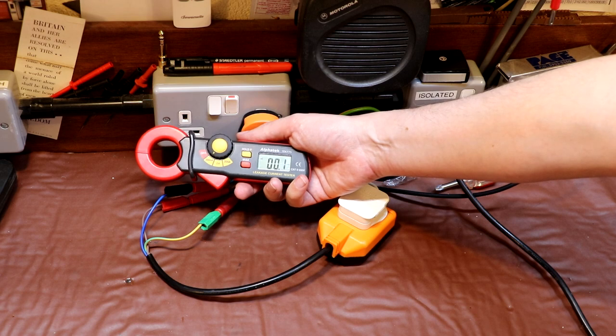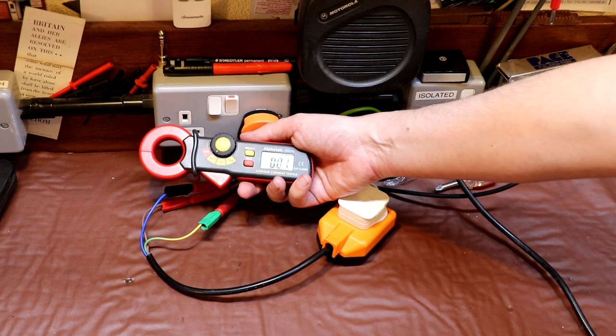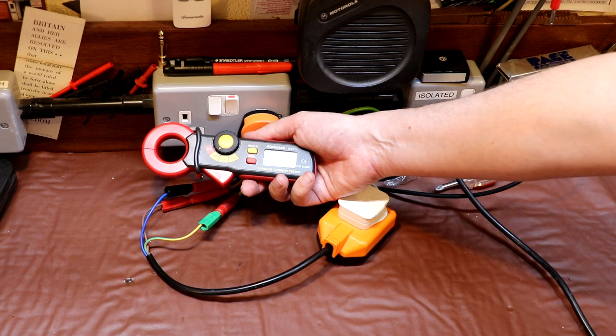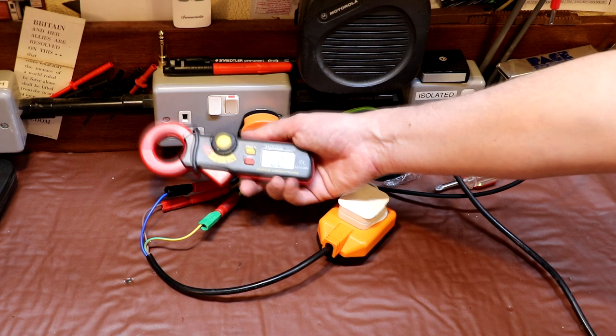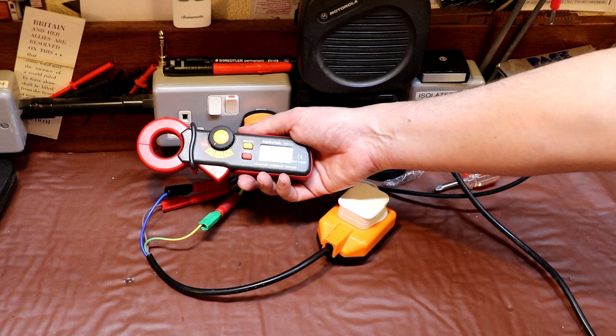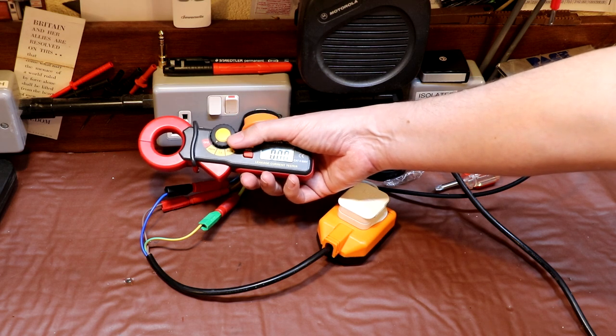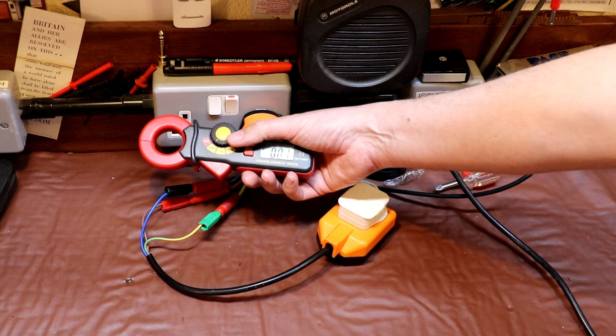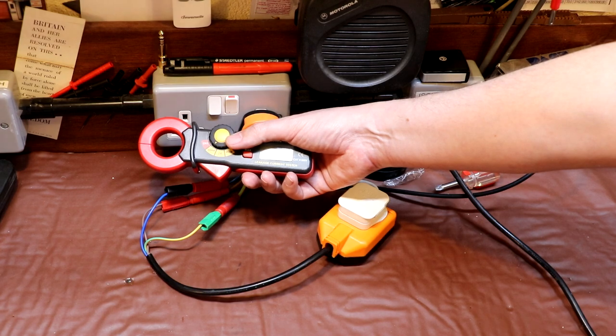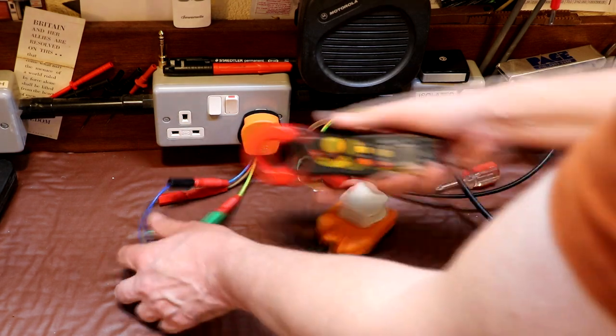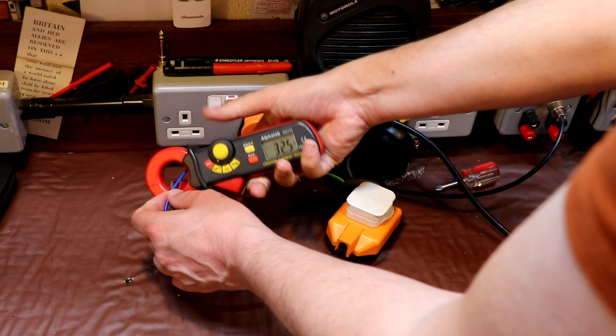So this clamp meter is made by Alphatec, and for those playing along at home, it's the Alphatec Tech 775. It is a little bit unfair to compare the Alphatec meter here to the KAIWEETS meter, because this particular meter is designed for measuring these very low leakage currents, and so it does have a 200 milliamps range, whereas the lowest range on our KAIWEETS meter is the 6 amps range. So I'm going to clip onto both our live and neutral wires again.